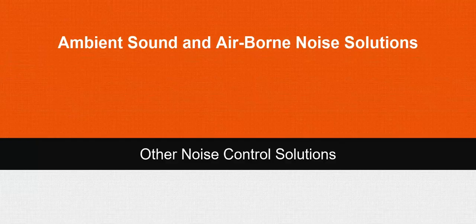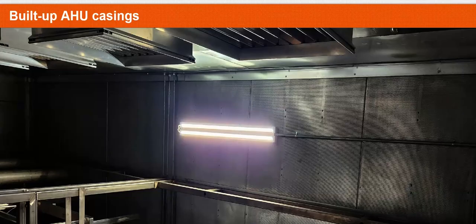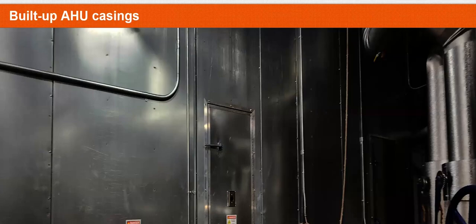We're going to move on now into seeing how we apply all this scientific approach into other noise control solutions. Another way you could use acoustical panels is to use them as the casing of the built-up air handling unit. In many cases, you already have existing mechanical rooms in the third floor, fifth floor, and you cannot bring a new unit. So you got to bring your filter bank, your fan bank, your coil section all in pieces and replace everything at the mechanical room, because these specific air handling units run at either 6 inches or 10 inches of pressure.